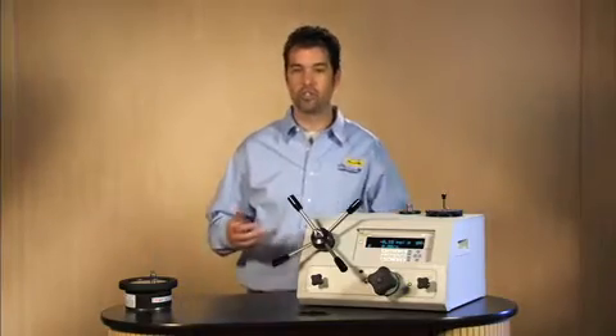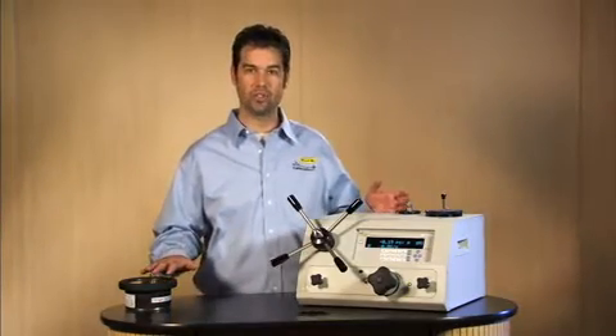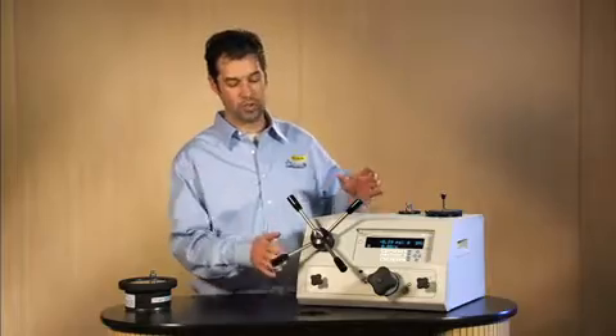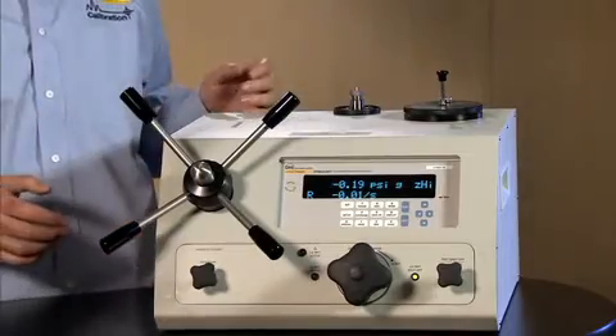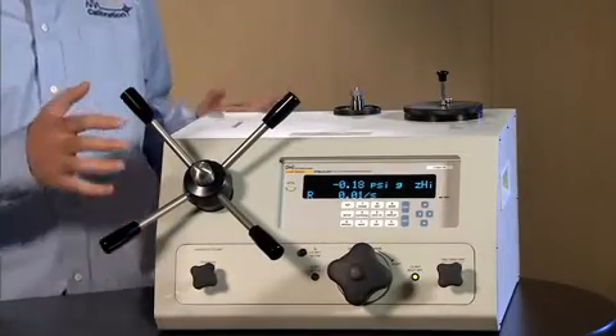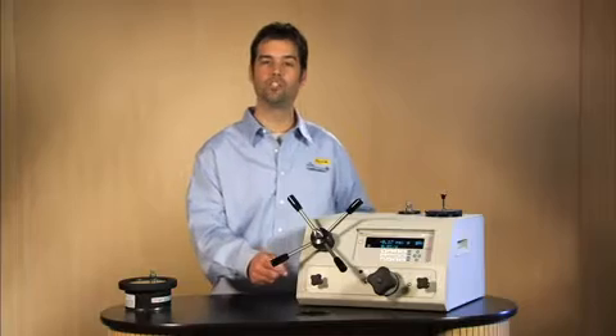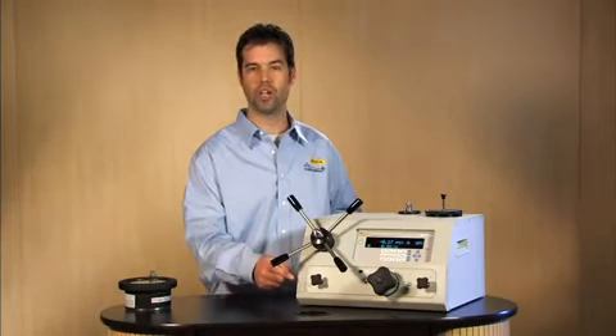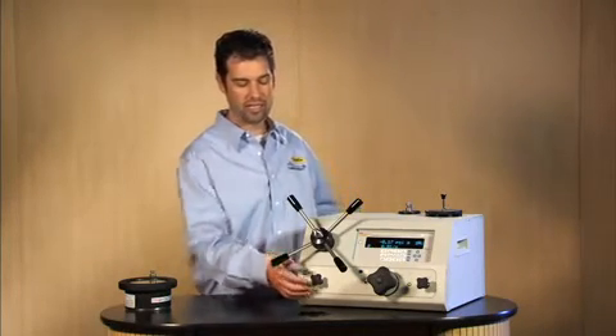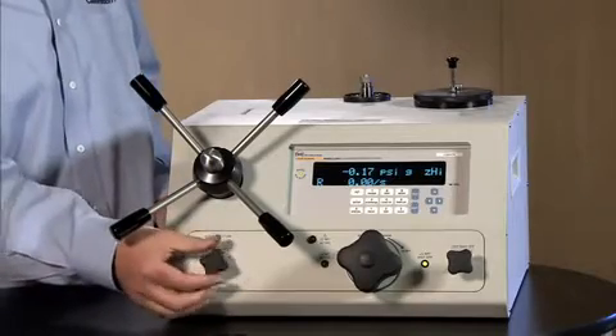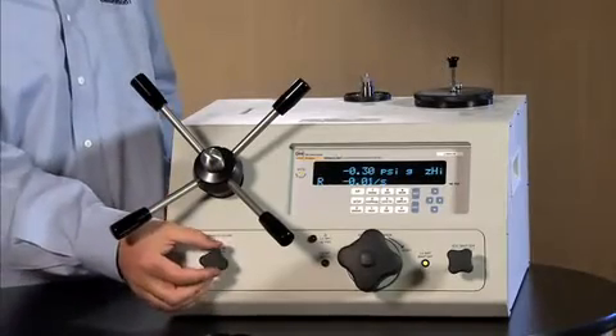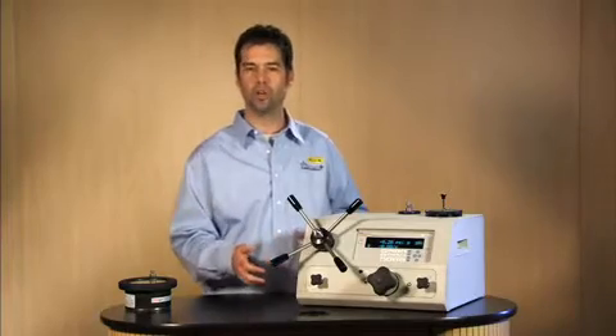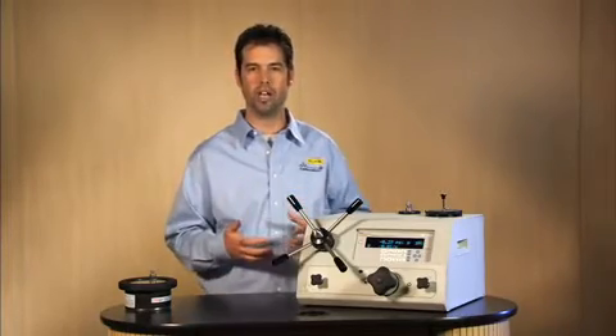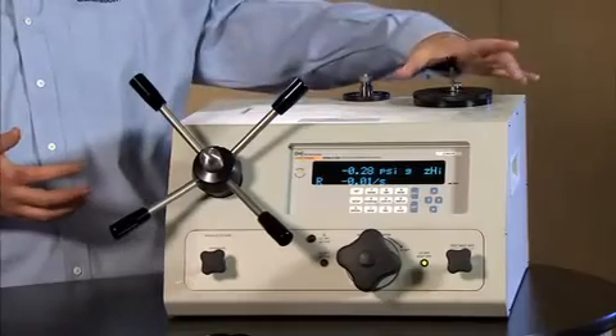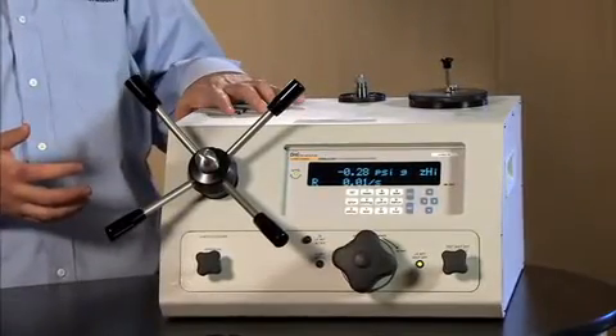Now we are ready to calibrate the gauge. What we need to do is put the valves in the correct orientation and back out the variable volume. Now we need to position the reservoir shutoff valve so that it is open. To open it, we want to go in the counterclockwise orientation. It doesn't have to be fully open, it just needs to be open enough to be able to pull fluid from the reservoir into the variable volume.